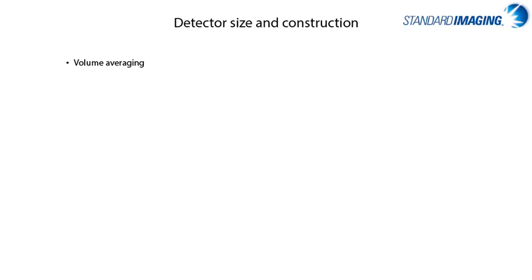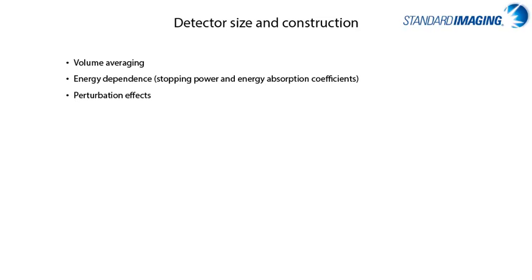and they are likely non-water equivalent or contain some non-water equivalent components. With these factors combined, there is a perturbation factor for any detector placed in a field which can exhibit volume averaging, energy dependence, and other perturbation factors which may or may not be uniform across field size, energies, or modalities. We'll consider each of these major effects individually in the coming slides.